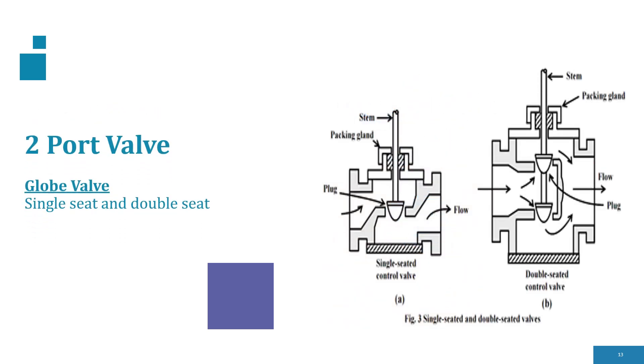A globe valve can be used for regulating flow or pressures as well as complete shut-off of flow. It may also be used as a pressure relief valve or as a check valve. Compared with a gate valve or ball valve, the globe valve has considerably higher pressure loss in the fully open position. Single-seated valves are one form of globe valve that are very common and simple in design.